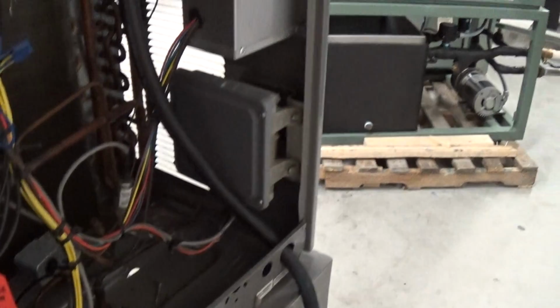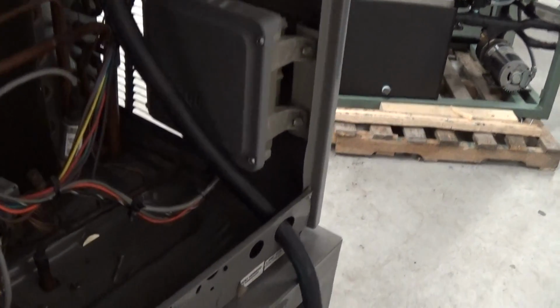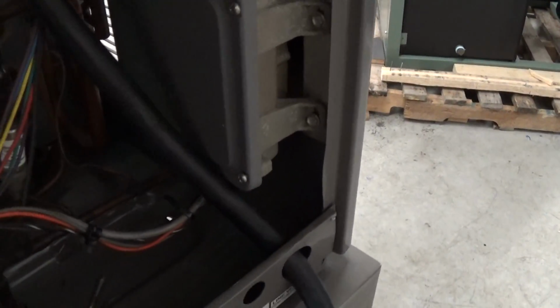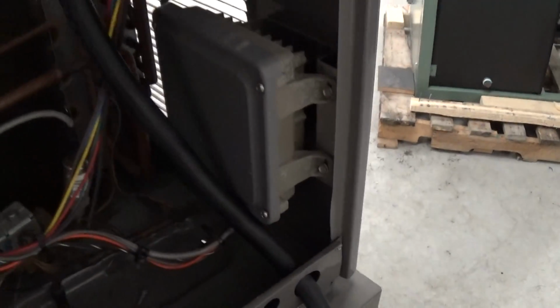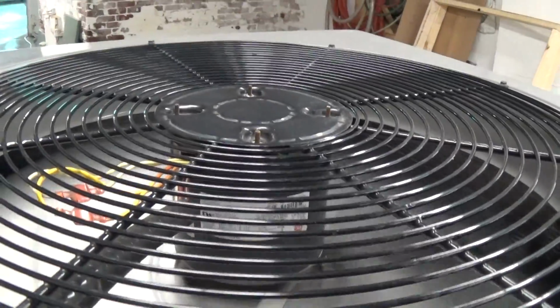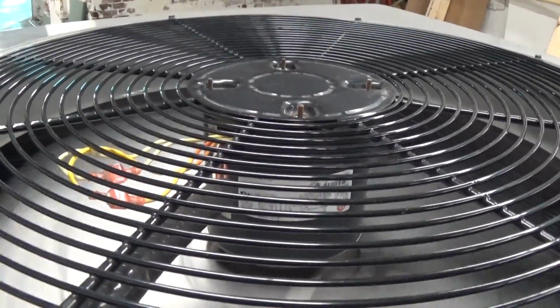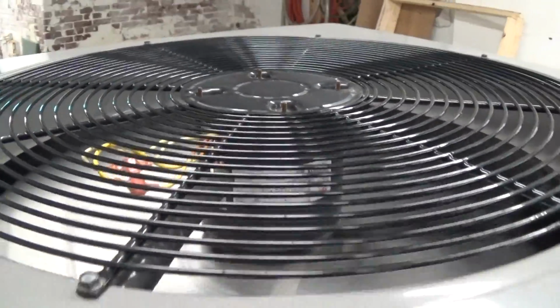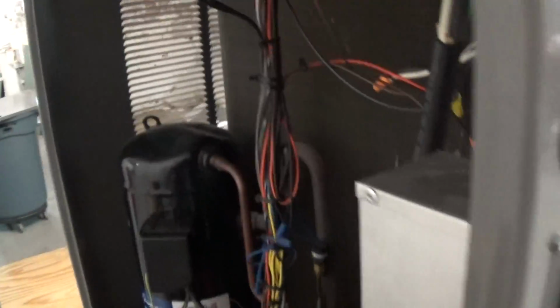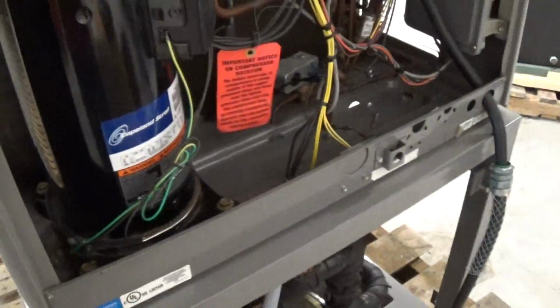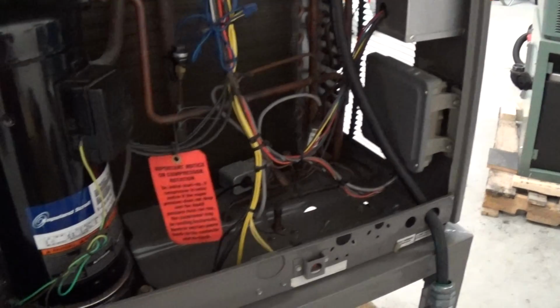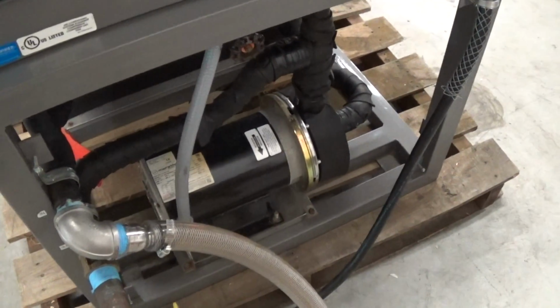the unit. This unit has the low ambient option, so we have our Johnson Controls P266 fan speed control, and you can hear the fan ramp up there. Nice smooth start. And a combination of that and on-off fan switching gives you some good low ambient capability. In the climate which we're going to, it's not going to be as critical, but it's still nice to have from an efficiency standpoint. Again, we have a 5 horsepower pump here.